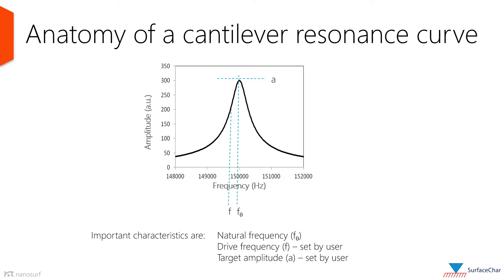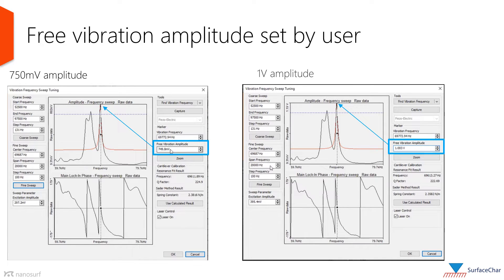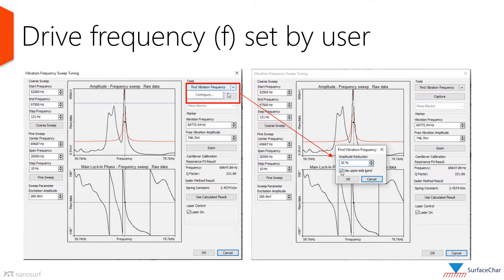Here we can see a resonance peak of a cantilever. The resonance, or natural frequency, is that at which the cantilever exhibits the highest oscillation amplitude. The drive frequency and amplitude are set by the user, and the excitation circuit attempts to reach the set parameters. An example of setting free amplitude in Nanosurf software is shown: the amplitude was set to 750 mV on the left and 1 V on the right. The excitation amplitude on the right went up to reach the desired free amplitude. The further the drive frequency is from the resonance peak, the more drive amplitude will be required.